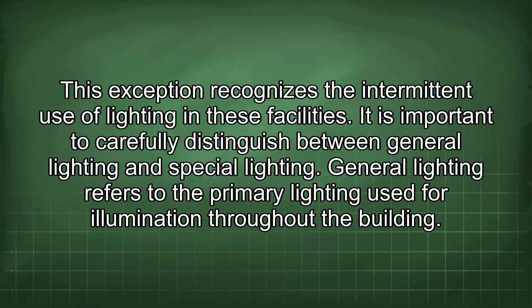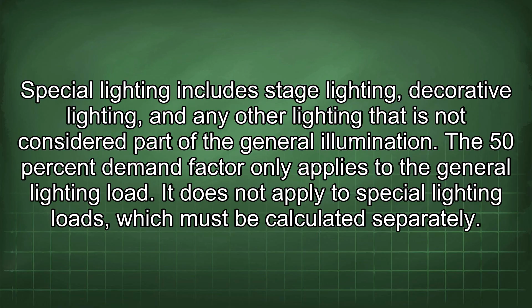It is important to carefully distinguish between general lighting and special lighting. General lighting refers to the primary lighting used for illumination throughout the building. Special lighting includes stage lighting, decorative lighting, and any other lighting that is not considered part of the general illumination. The 50% demand factor only applies to the general lighting load. It does not apply to special lighting loads, which must be calculated separately.